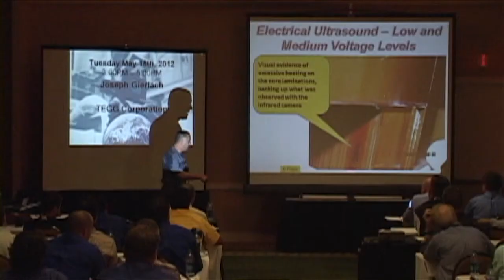It happened to be highest here. Because it's so directional, it allows me to isolate down the general area where it's coming from - that tells me where to focus my efforts on the shutdown, doesn't it? So digging into that a little deeper, you can see on this core piece right here - what does that look like to you? It's burnt.